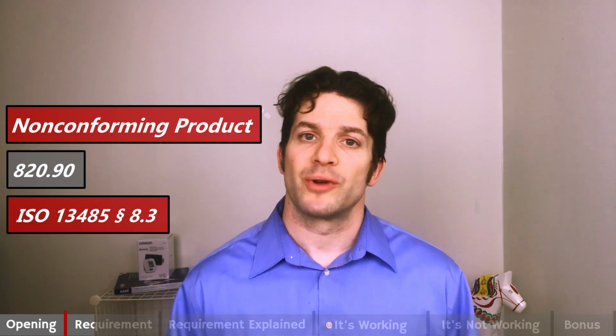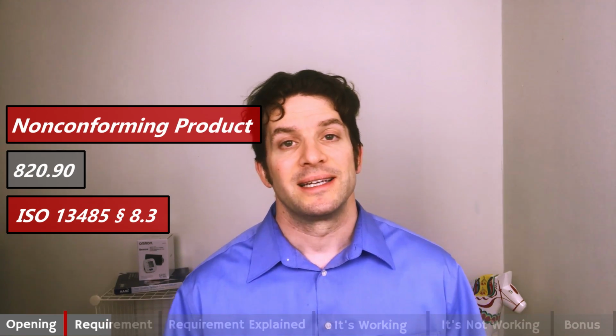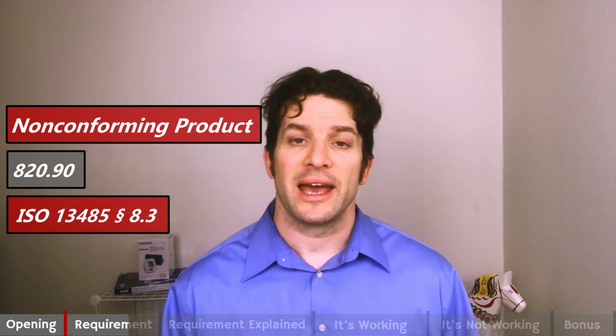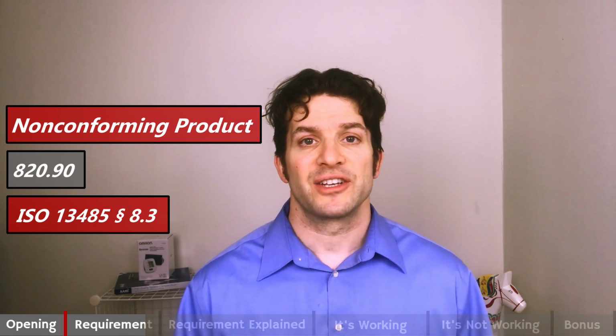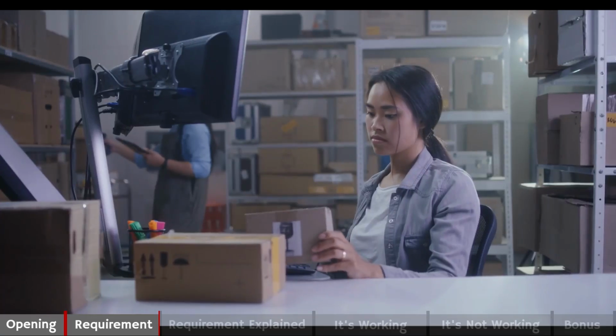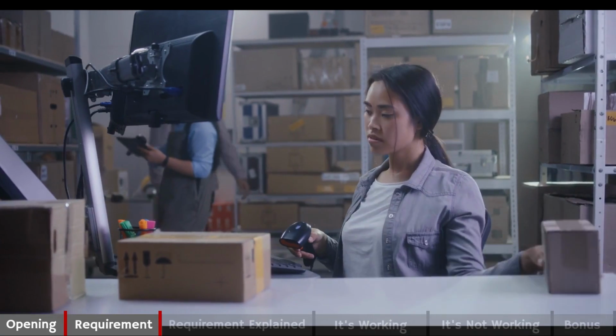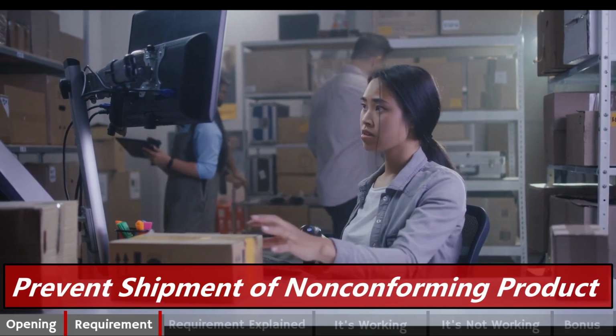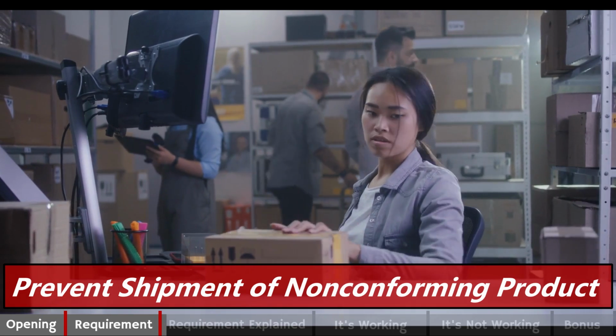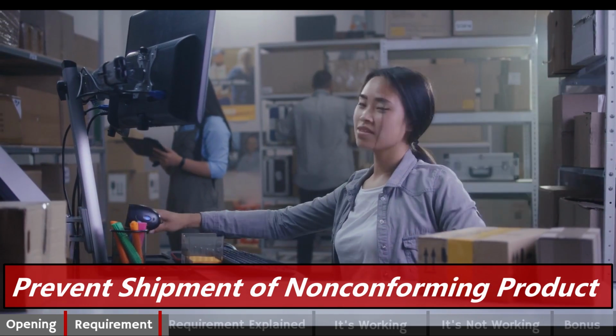Our topic, Nonconforming Product, comes directly from 820.90 and 13485 section 8.3. Nonconforming product in 5 words: Prevent shipment of nonconforming product. We have to have a procedure that outlines how we control and manage and disposition nonconforming product.